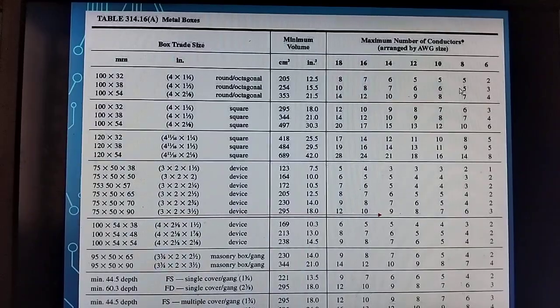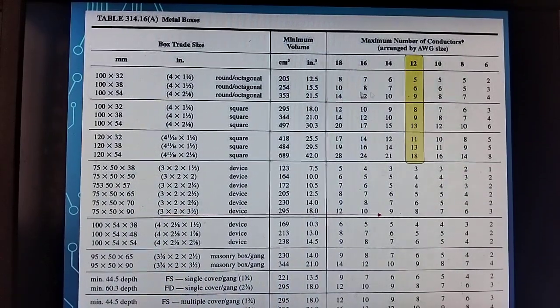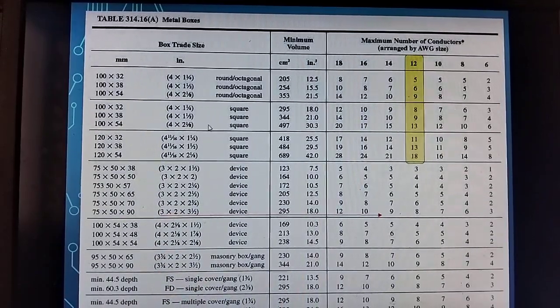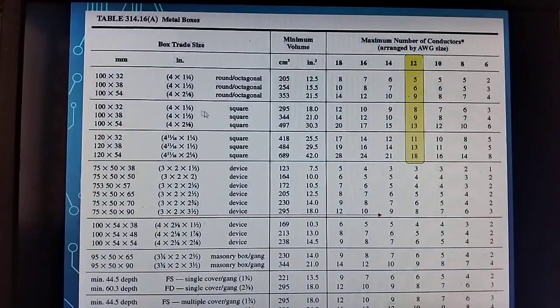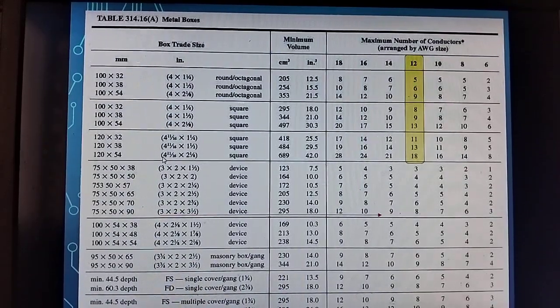Let's say you put 12 electrical wires, but then you use the wrong size of junction box. Let's say you use only a 4 by 2 and 1/8 round octagonal box. How many is allowed only for size 12? Let's say here we use the 4 by 2 and 1/8. You are only allowed 9, so your octagonal junction box is undersized. What you will do then is replace it with a bigger square junction box. Instead of the 4 by 2 and 1/8, replace with a square, bigger one. Let's say this 4 and 11/16 by 2 and 1/8. It can accommodate 13.